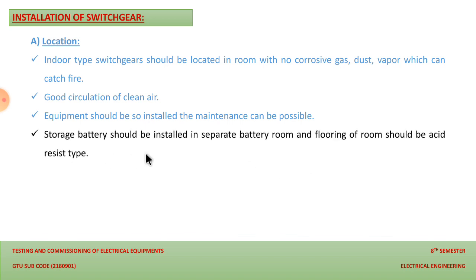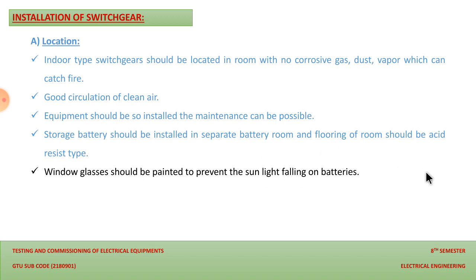And the storage battery should be installed in a separate battery room, because if an accident takes place in future, as per the Indian standard, we should provide a separate battery room for the operation of the switchgear. And the flooring of the room should be acid-resistant type. Industries deal with many hazardous things like acid and oils, so the floor must be acid-resistant, because otherwise it can harm our utility. And window glasses should be painted to prevent sunlight falling on the batteries. This is an important point for the long-lasting operation of the battery.